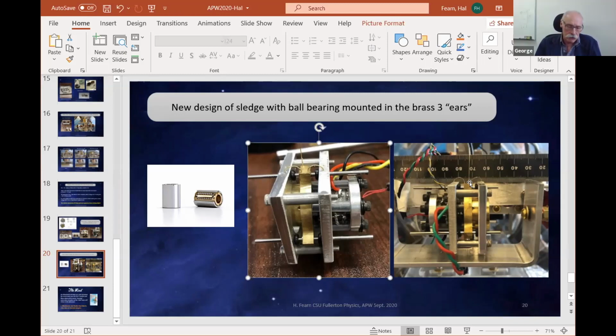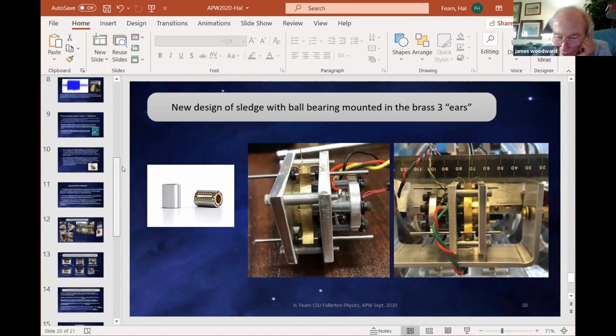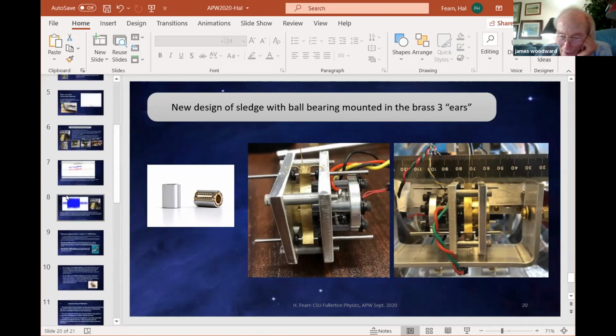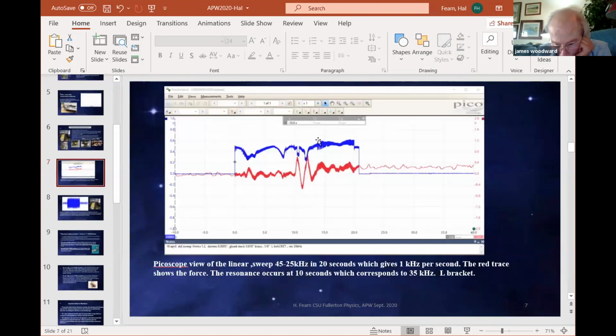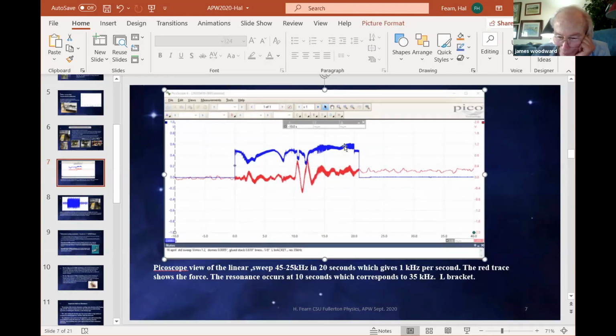I wonder where it's coming from - I didn't check the exact frequency, I should have. It's noise in the amplifier. We've had problems partly with that and partly with contacts. I used some Molex contacts for the power transfer from the cables to the wiring on the balance itself. We've replaced them with Amphenol gold-plated contacts recently, and it's pretty much gone away. But occasionally, our experiment kills amplifiers if you really push it - many amplifiers, though they don't die catastrophically. Well, they do eventually.